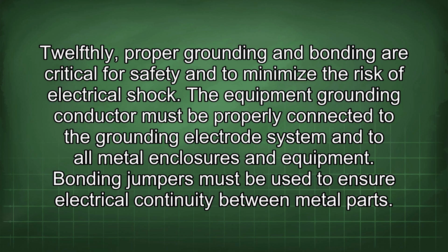12thly, proper grounding and bonding are critical for safety and to minimize the risk of electrical shock. The equipment grounding conductor must be properly connected to the grounding electrode system and to all metal enclosures and equipment. Bonding jumpers must be used to ensure electrical continuity between metal parts.